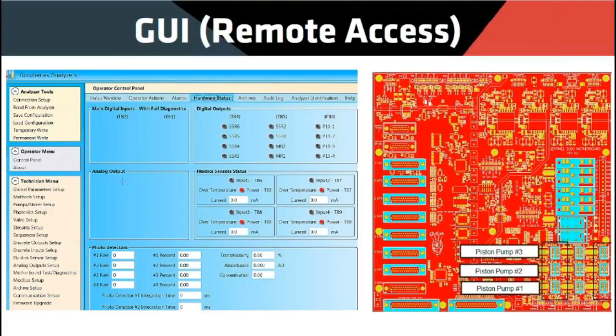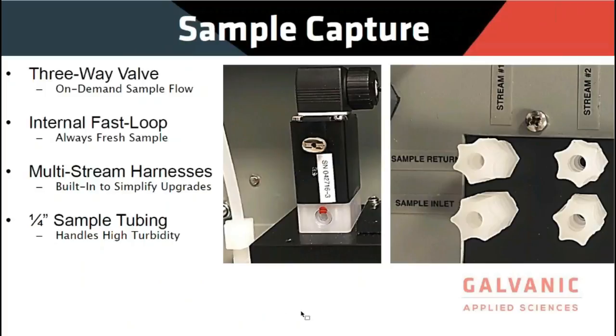We're able to go through the different setup menus, change outputs, play around with the methods. And what's nice is we can actually see all the active components. So on the right side, on the red image, you can see piston pump 3, 2, 1. So when you put your mouse cursor over it, it will actually appear, which is very handy. You have 3-way valves. What this means is that you're going to get on-demand sample flow. When we're not taking a sample, it's either going to go back to the process at a lower pressure or to a waste stream. And so this internal fast loop means it's always a fresh, real-time sample. As I mentioned, built-in stream harnesses, and we have that wide sample tubing for the high turbidity.